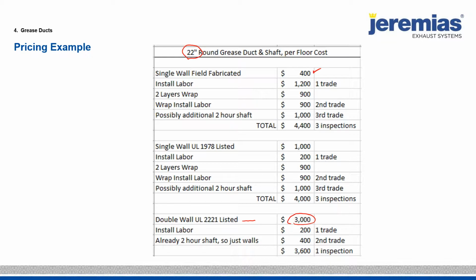But then he has to install that. It takes longer to install. Then he has to buy the insulation. They have to wrap the insulation, and they still don't have a real shaft, so they may have to put an additional 2-hour rated shaft in. So we're looking at $4,400 per floor versus the expensive system down here. They're simply connecting the system together, and you don't have to worry about a fire rated shaft. You can just put a standard wall construction up, not having the expensive fire rated doors. So what we want to look at are these numbers here, 3,600 per floor versus 4,400. Who benefits is actually the owner of the building.